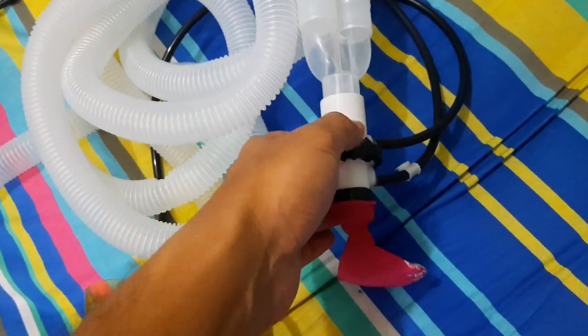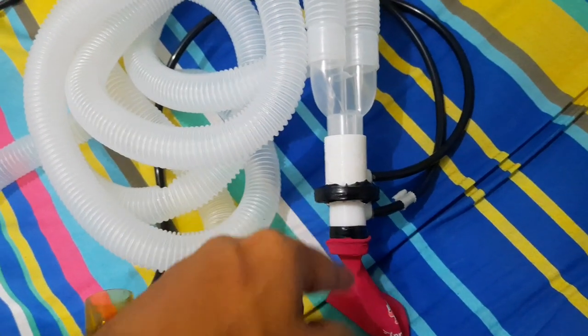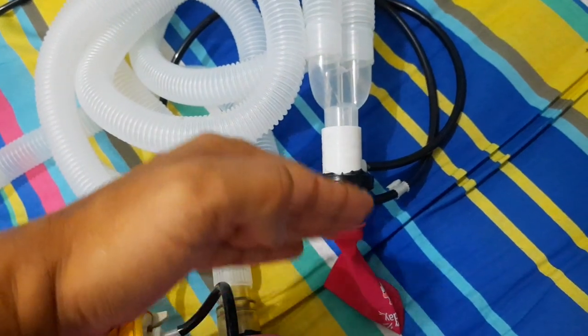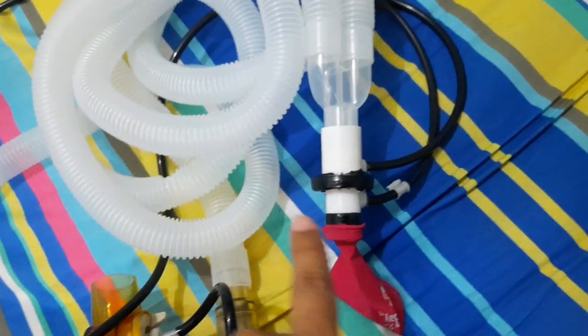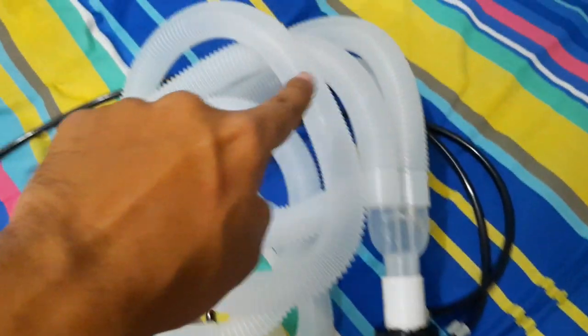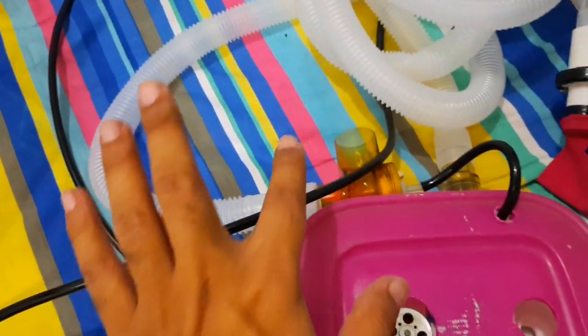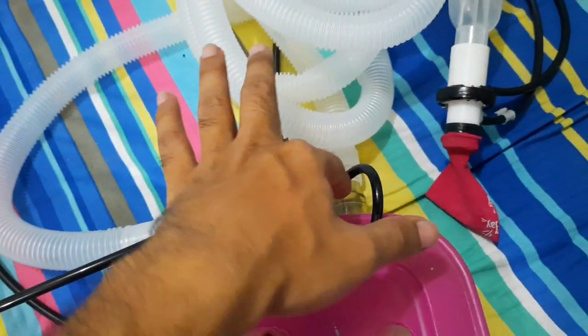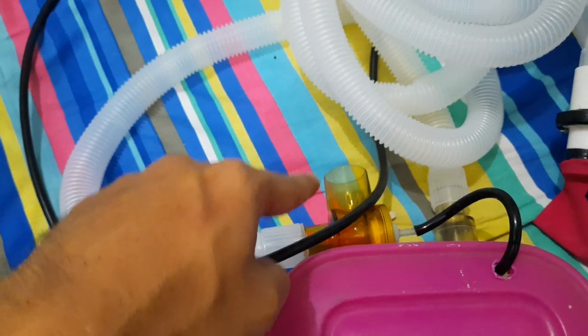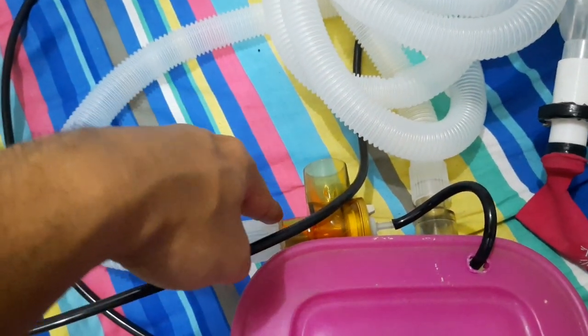One advantage of this orifice tube is that it is bidirectional. Although both directions are not the same, we can manage it. This is the pressure circuit, and this is the PEEP valve and one-way valve. This PEEP valve is from another ventilator.